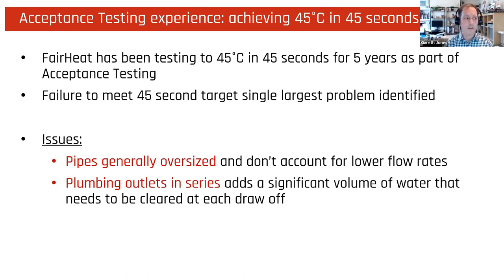problem that we've identified. Issues around that are pipes are generally oversized, so they don't account for lower flow rates, so people haven't made that change in design. And also we've seen that plumbing outlets are often plumbed in series, so you go through to a bathroom at a large diameter and then go off, for example, to a kitchen sink from there, which adds a significant volume of water that needs to be cleared at each draw off.